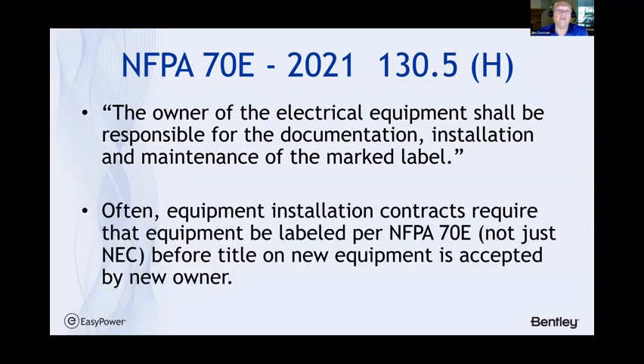So even if we have a contractor doing the work, they don't own the equipment. They may contract to do some kind of labeling, but ultimately it's the owner of the equipment that has the responsibility for making sure that's done. And so that's the reason equipment installation contracts often require that equipment be labeled per NFPA 70E, not just the National Electrical Code, before title is accepted on new equipment.